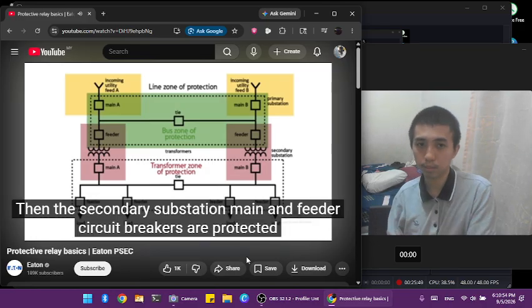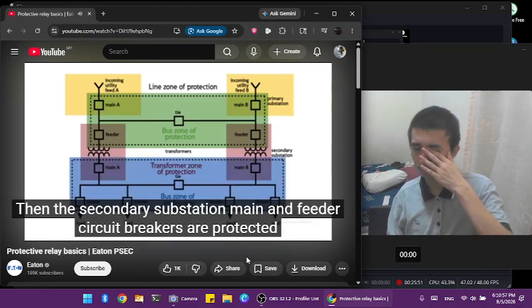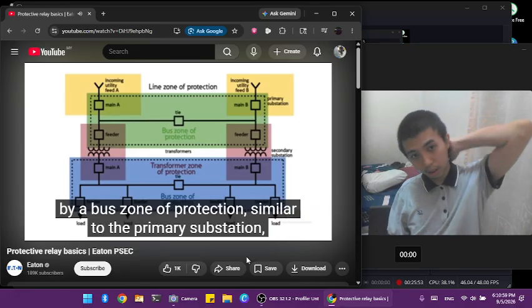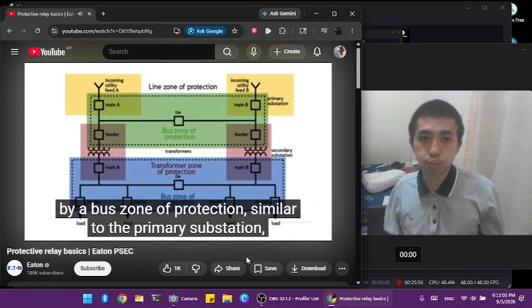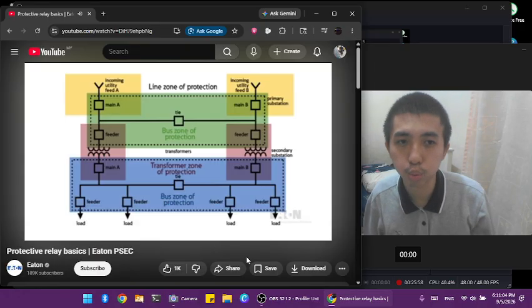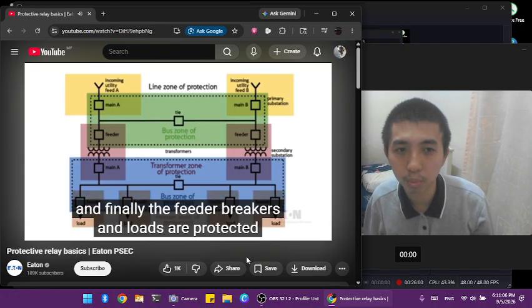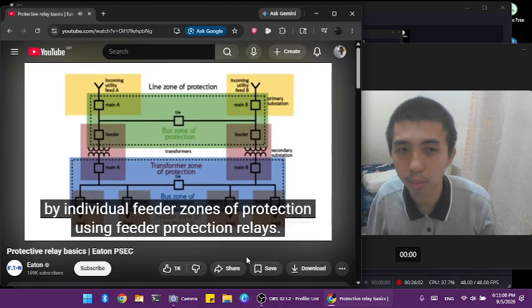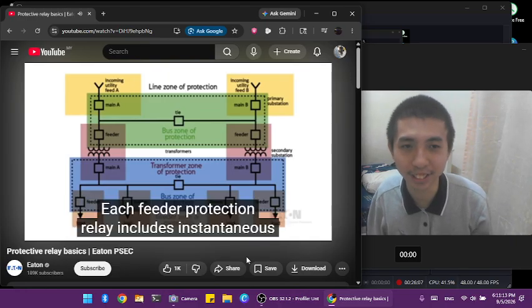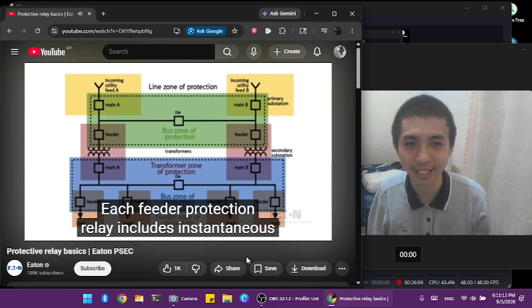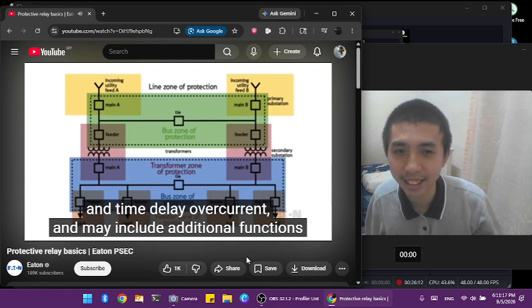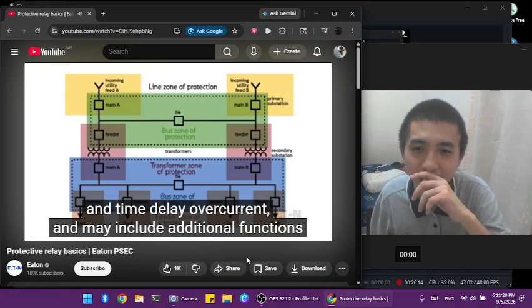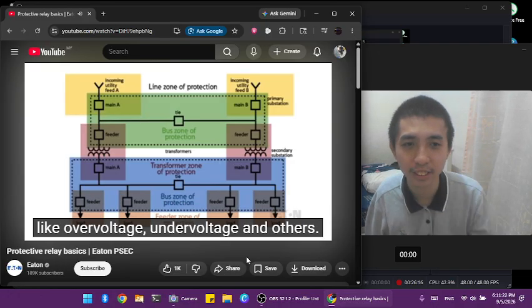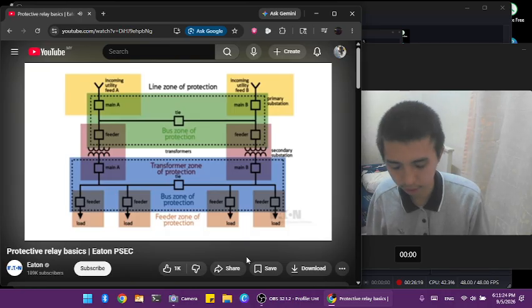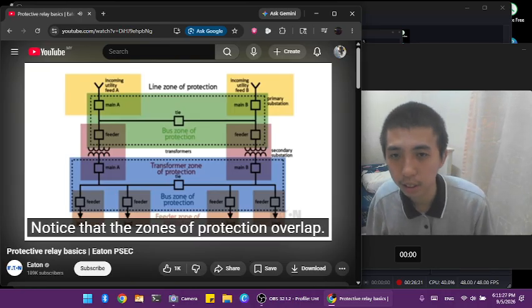Then, the secondary substation main and feeder circuit breakers are protected by a bus zone of protection, similar to the primary substation. And finally, the feeder breakers and loads are protected by individual feeder zones of protection using feeder protection relays. Each feeder protection relay includes instantaneous and time delay overcurrent and may include additional functions like overvoltage, undervoltage, and others. Notice that the zones of protection overlap.